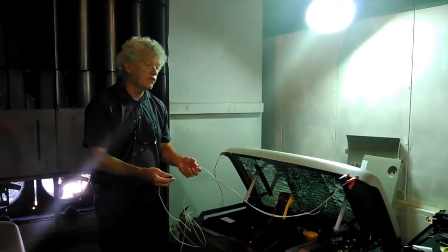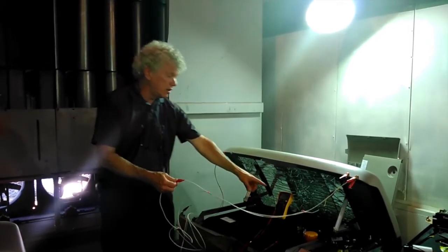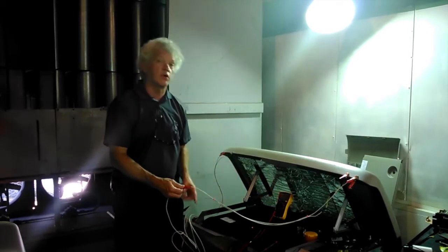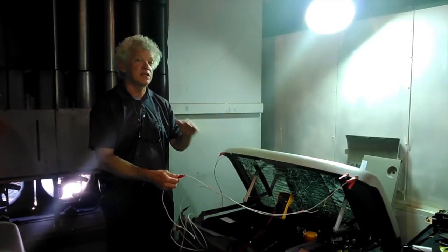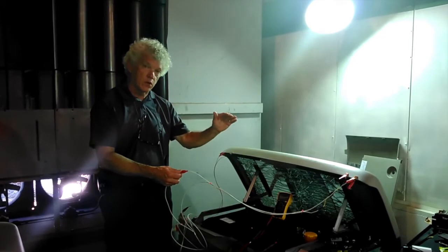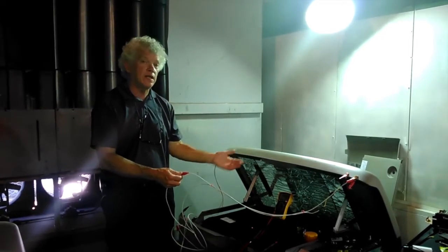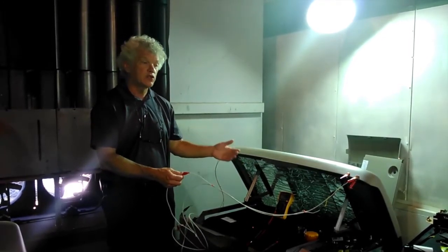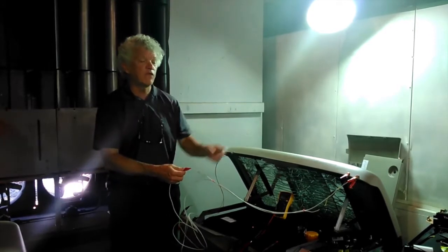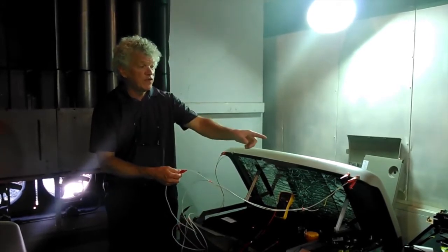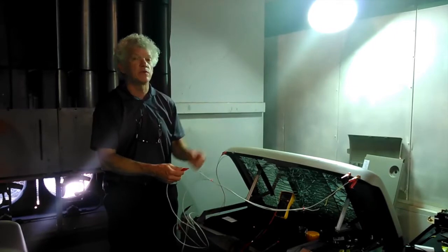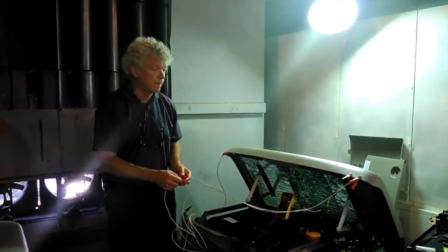So what we're looking for is we want to make sure that the current that's going to the rotor in that circuit maintains an equal and steady current, approximately 1.8 to 2 amps, while it's running. Then we want to see what our voltages are on our 55 and 66, and then we'll compare them to what it gives us in the service manual.